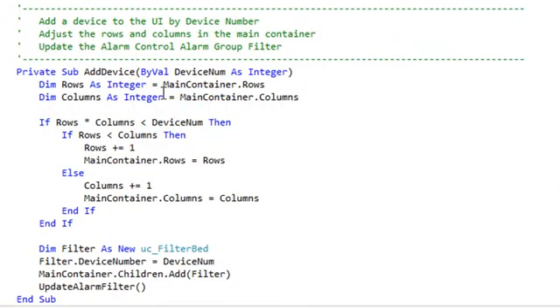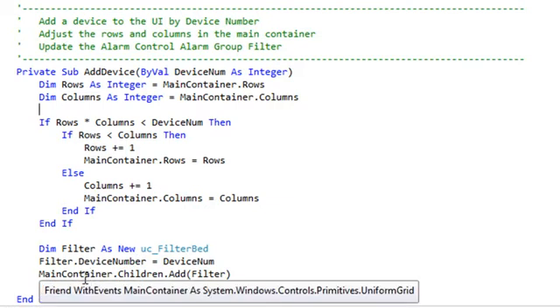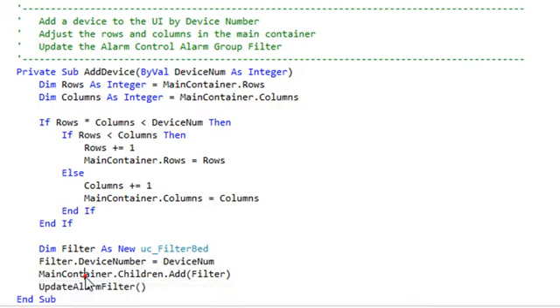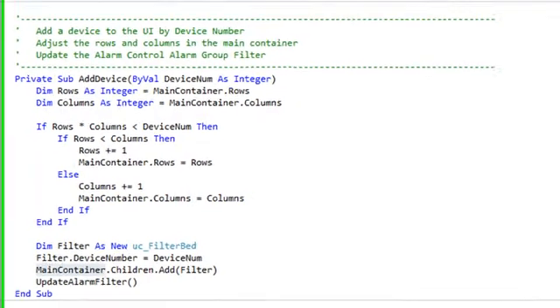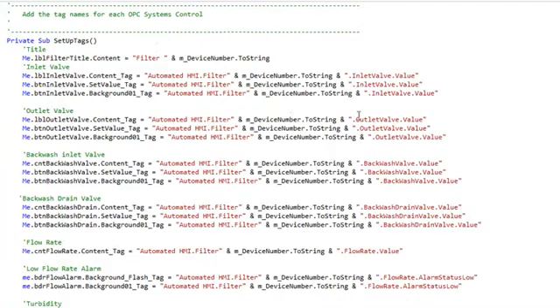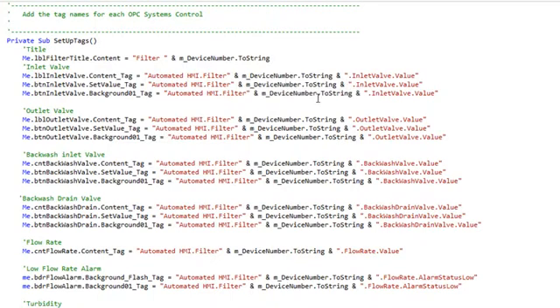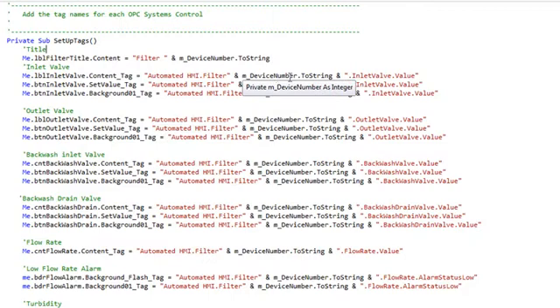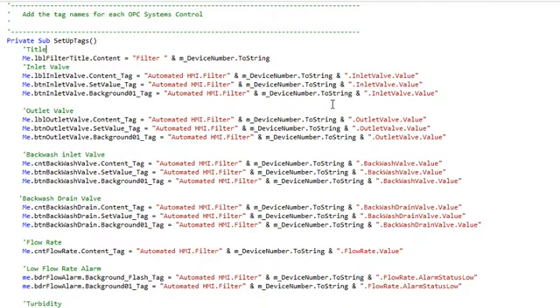Here we see the method Add Device, where it's adding a filter to the main window. And if we look at the code for the filter bed, the HMI controls are set to the tag names based upon which filter we're adding. The device number ranges from 1 to 25, depending upon how many filters you've added.